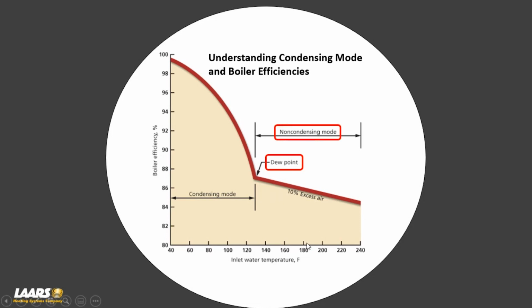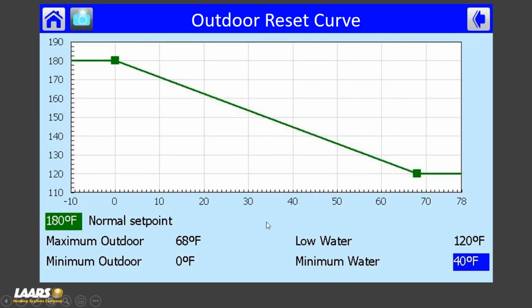So if I'm supplying 180 out to a system and returning at 160, I'm in non-condensing mode. However, as it warms up outside, now if I'm supplying 140 to a system and returning back at 120, you'll see your efficiencies start to go up around 90%. Why? Because now you're in condensing mode. So that's important to understand. And I'm going to show a basic outdoor reset curve here. On this left-hand column, this is your supply temperature to a system. And in this example, I chose 0 degrees at 180 degrees. And again, you utilize this depending on your system. I'm talking about baseboard heat that you may need 180 on a 0 degree day, but maybe you've got hydro air. Hydro air maybe only needs 160 on a 0 degree day. And then you maybe have in-floor radiant. Your max temperature there might be 120 or 130. And you would adjust your curve.